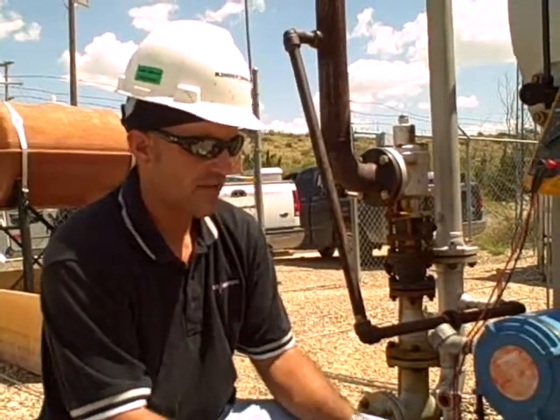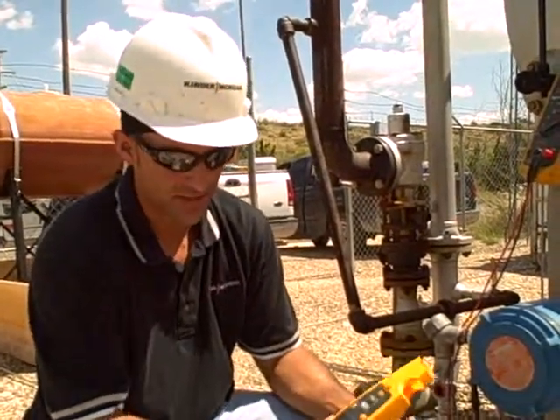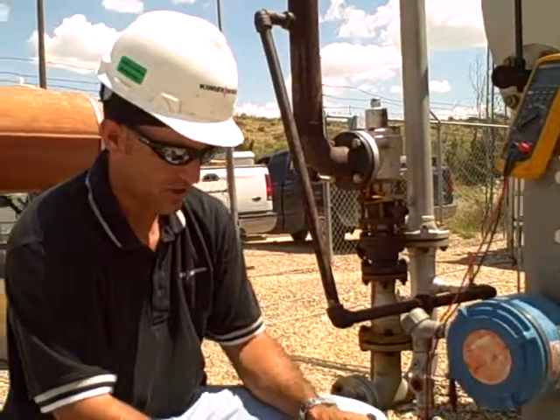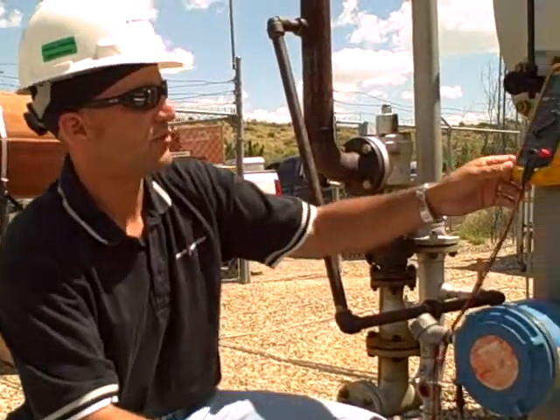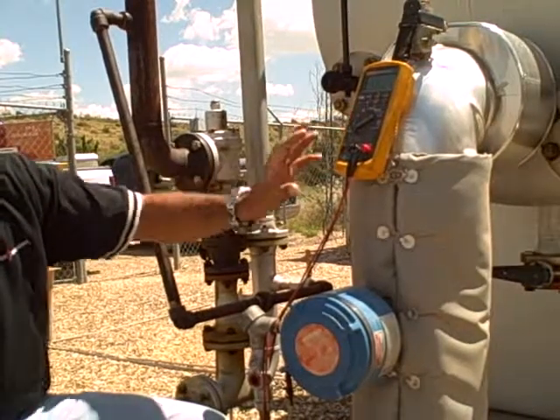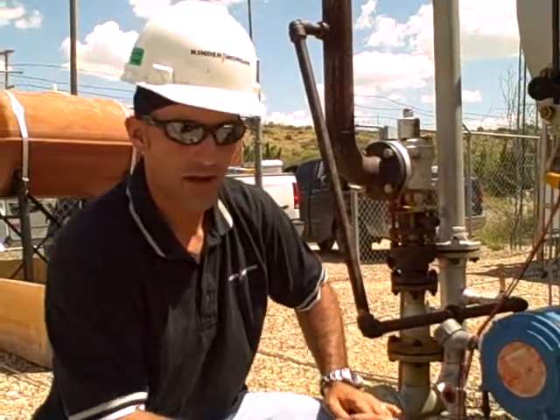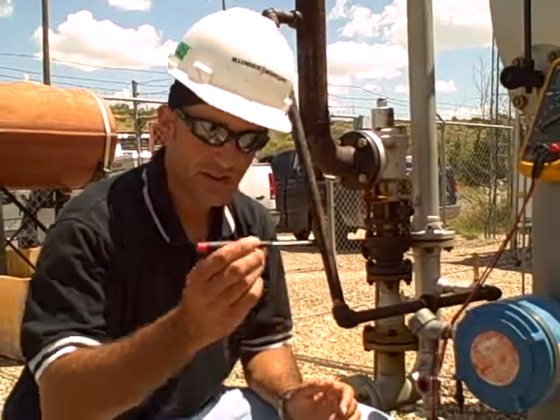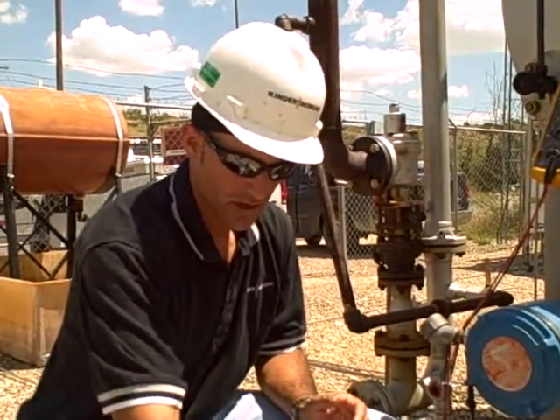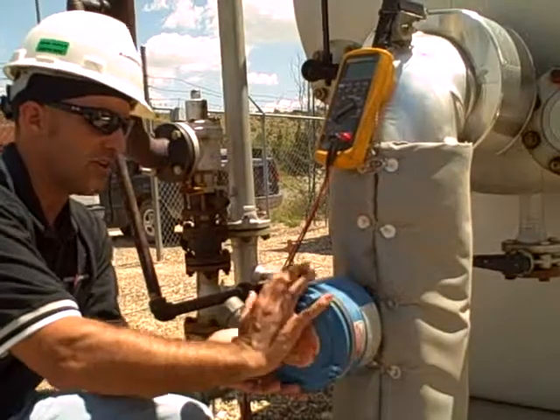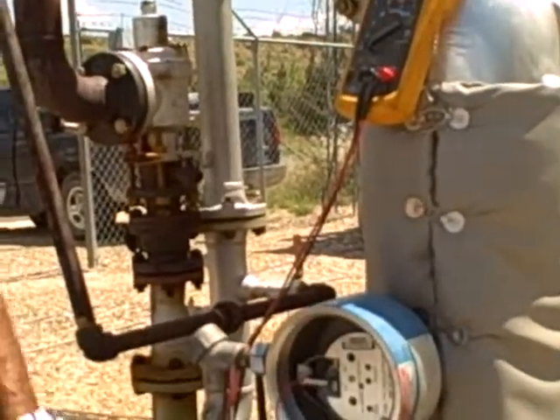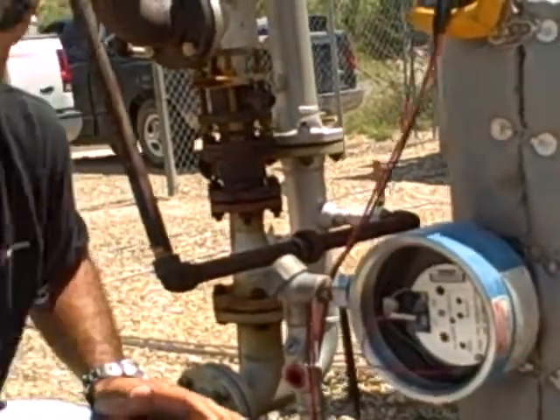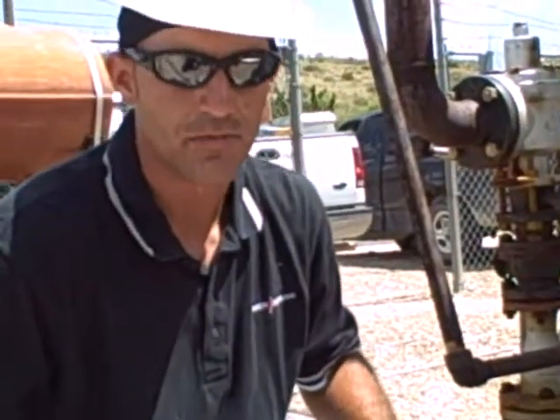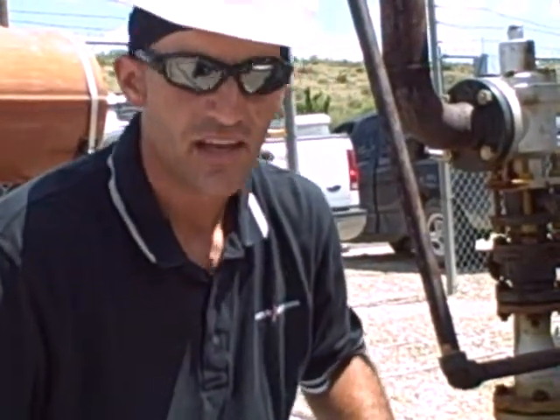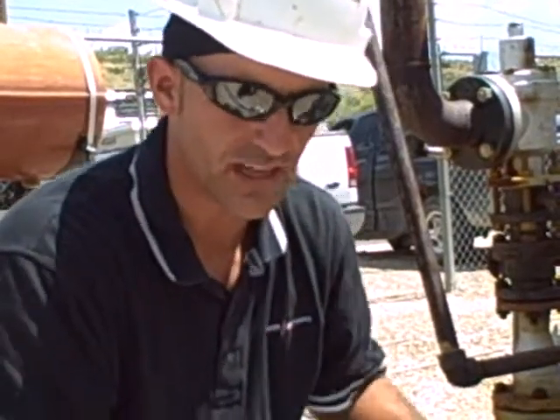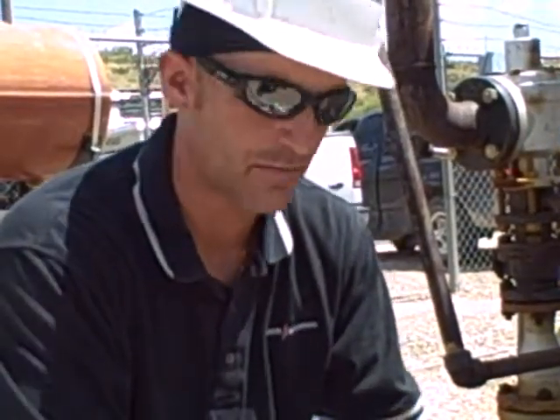The first thing you have to have is, right here I have a Fluke 771 DC amp clamp, which reads milliamps. I have a Fluke 787 process meter, which I use to measure my voltage, and I also have a small calibration screwdriver. The first thing we're going to do is take this lid off. While you're getting your stuff ready, you need to have your operator go ahead and get a shakeout so you know what to set your BS&W probe for. I already have my operator do that, and I need to set this to 3% basic sediment and water.